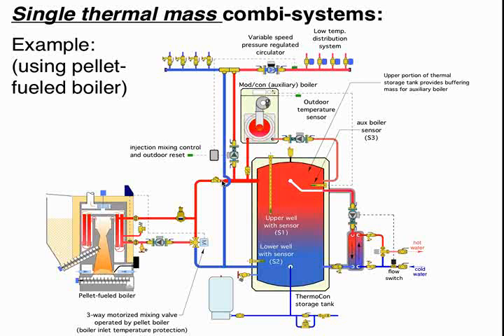And obviously, steel boilers and cast iron boilers have proven that in closed systems, any initial oxidation that you have is not going to be a continuing process. Again, I'm presupposing everything remains a closed system. If you were going to have an open system and you still wanted to use a tank, like a ThermoCon tank, the glass lining should protect it. I mean, the glass lining was developed around potable water, fresh water. So in a true closed-loop application, I don't see it as a requirement, but it's not an impediment either.